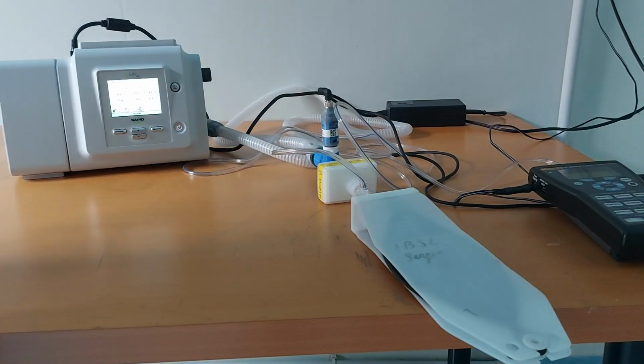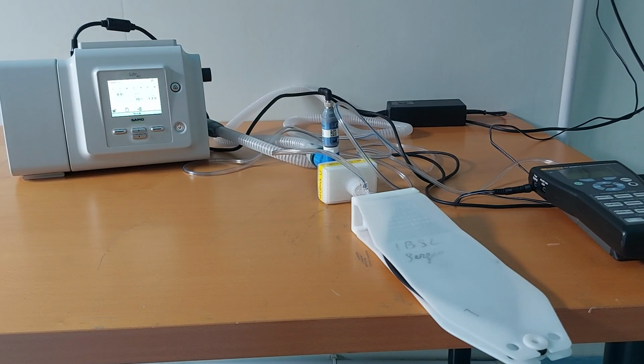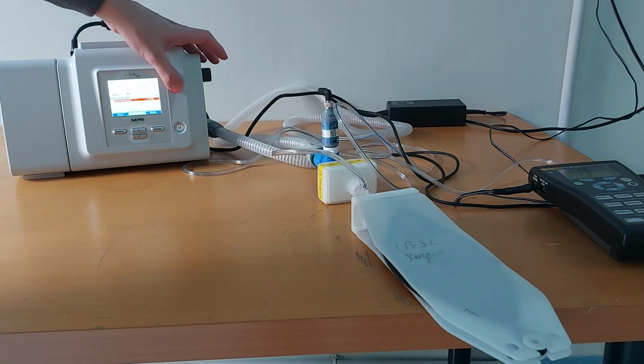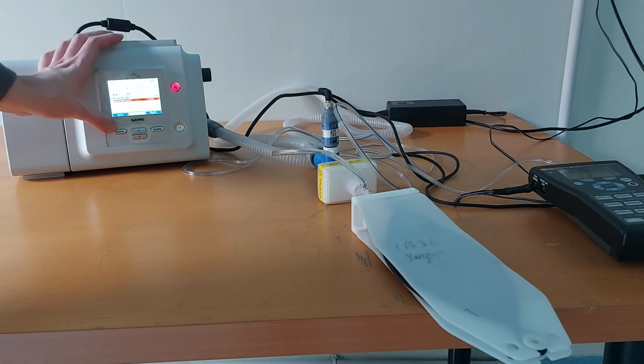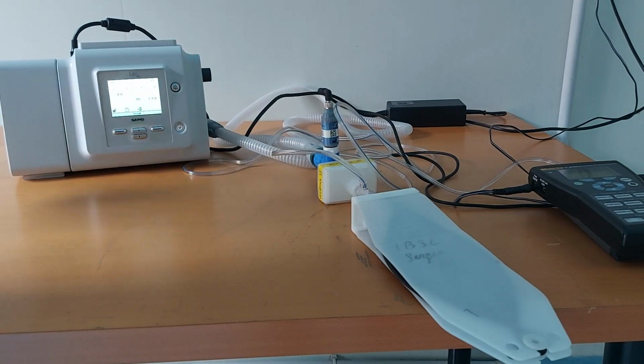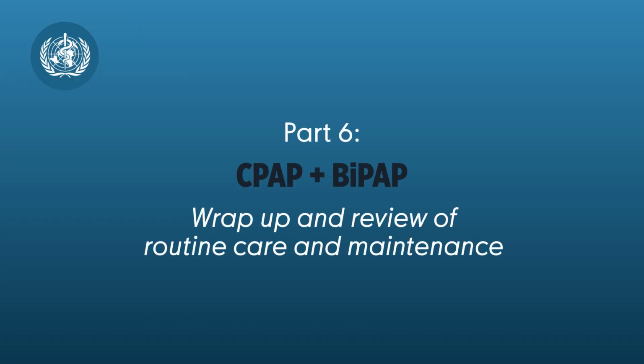Disconnect the circuit at the patient connector to activate the low pressure alarm. Verify that the low pressure alarm activates audibly and visually, and that the alarm activates within the manufacturer's specified time delay. Reattach the breathing circuit and verify that the indicator remains lit until manually reset. You've now completed acceptance testing on your new CPAP or BiPAP.